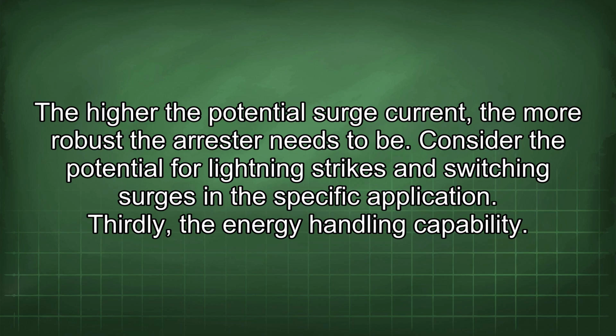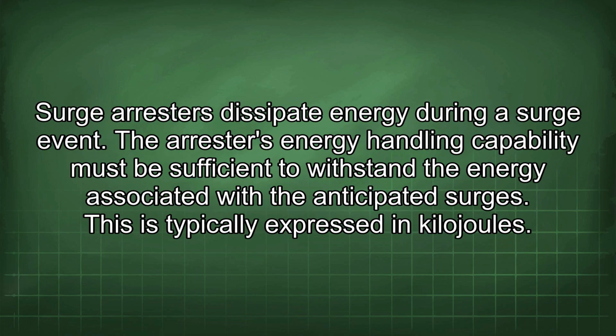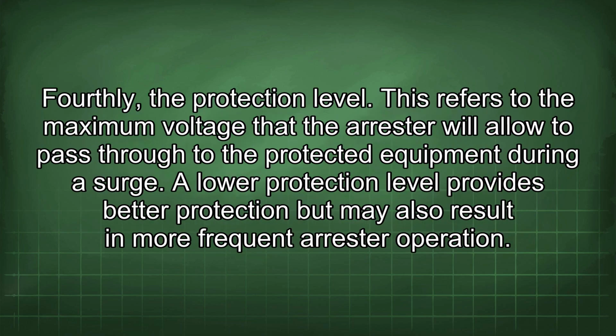Thirdly, the energy handling capability. Surge arresters dissipate energy during a surge event. The arrestor's energy handling capability must be sufficient to withstand the energy associated with the anticipated surges. This is typically expressed in kilojoules. Fourthly, the protection level. This refers to the maximum voltage that the arrestor will allow to pass through to the protected equipment during a surge. A low protection level provides better protection but may also result in more frequent arrestor operation.